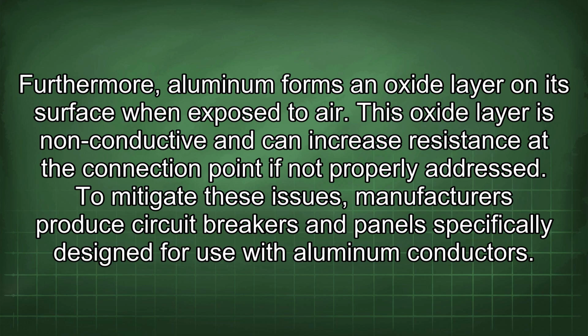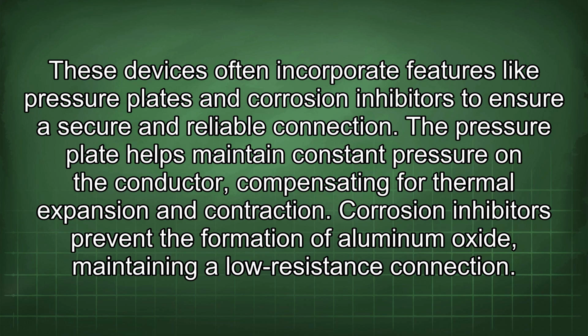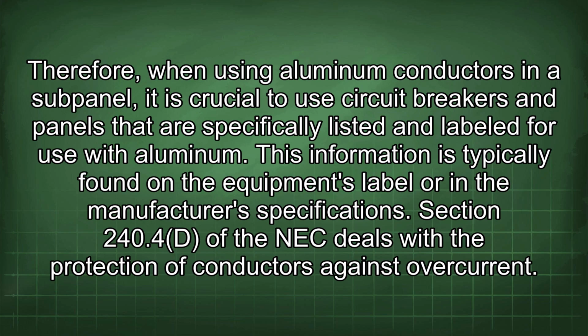To mitigate these issues, manufacturers produce circuit breakers and panels specifically designed for use with aluminum conductors. These devices often incorporate features like pressure plates and corrosion inhibitors to ensure a secure and reliable connection. The pressure plate helps maintain constant pressure on the conductor, compensating for thermal expansion and contraction. Corrosion inhibitors prevent the formation of aluminum oxide, maintaining a low resistance connection. Therefore, when using aluminum conductors in a subpanel, it is crucial to use circuit breakers and panels that are specifically listed and labeled for use with aluminum. This information is typically found on the equipment's label or in the manufacturer's specifications.